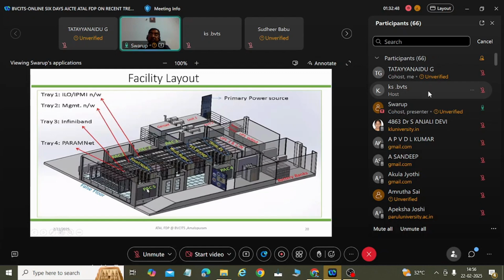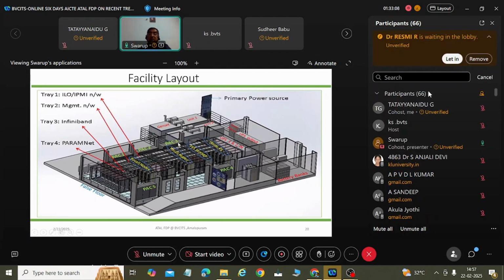So that is why, when power goes, you have to ensure that by the time the next power source comes up, like say the DG set triggers up and then provides your power, the cooling should be ensured. Whatever the gap is, whether it is 1 minute or 2 minutes, you have to ensure that enough cooling is available, so that the overall temperature is maintained and it can continue the work.